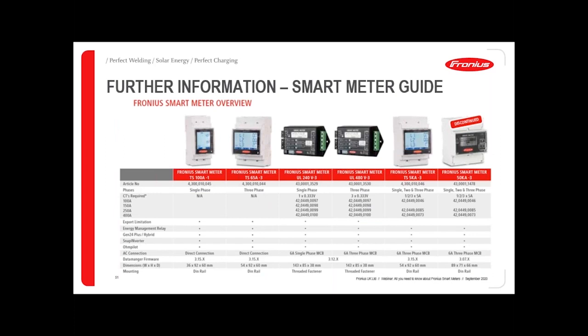On the back page of the document, you'll see a list of all the different meters and the CTs required for each meter, whether it be 100 amp through to 400. If you have a meter that requires larger CTs, you'd need to source those separately. Fronius offer the sizes there, but it may be that you have a larger system which is not readily available. There are obviously many wholesalers and distributors for CTs on larger bespoke sites. As long as they have the correct output and the correct accuracy class, you're able to source those separately.